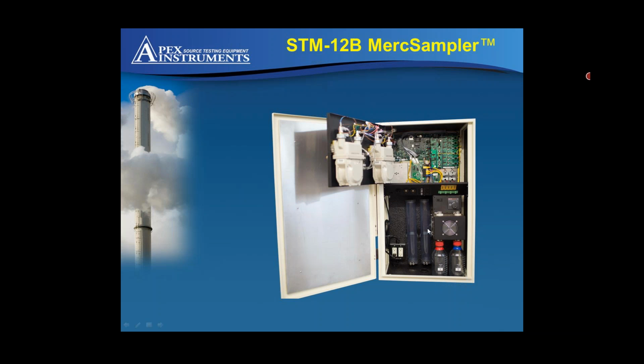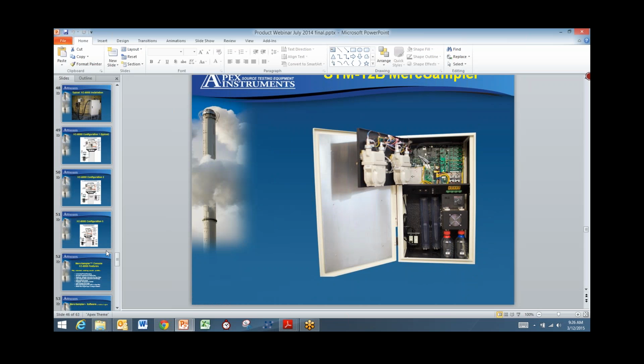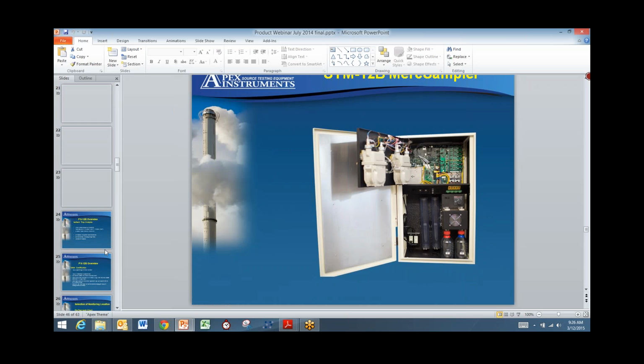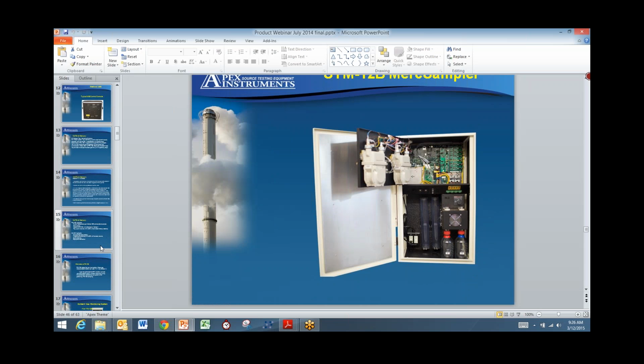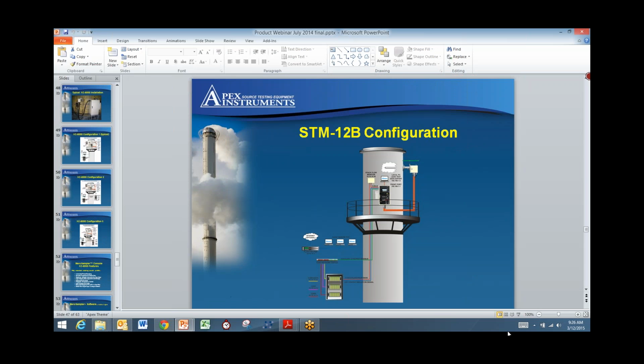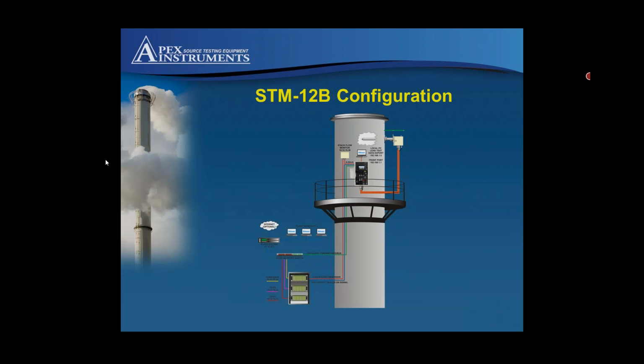How do we draw a sample? Is it through a pump that's in the panel, or do we need to provide instrument air? No, no instrument air is required. The actual pumps and all are in the console. You can't see it from this picture, but there's a manifold assembly that has the pumps, the mass flow sensors, the vac sensors, proportional valves. So all that's like one unit inside of there, but no, you don't need any plant air or any kind of an external pump. It's all self-sufficient, self-contained.